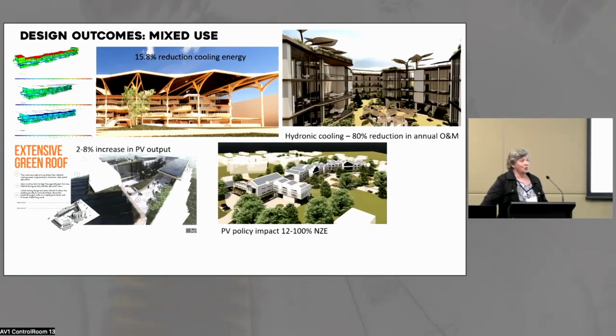If you reduce the cooling load in the tropical region to a maximum of 50 watts per square metre, it then actually makes a hydronic cooling system a technical feasibility, and a hydronic cooling system uses 80% less energy and less cost than running a chilled water system or a variable refrigerant system. That was verified by one of our consultants.